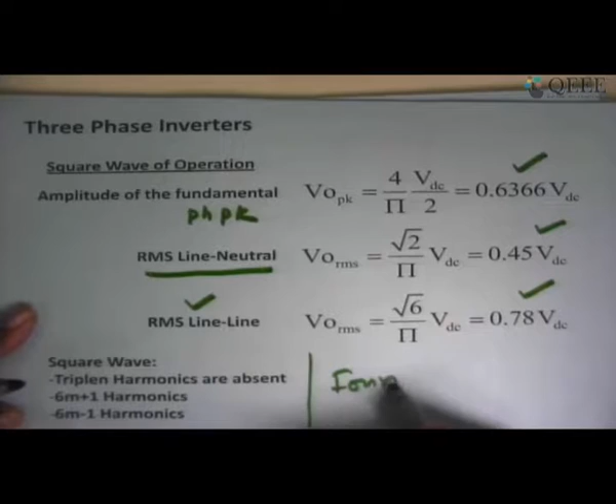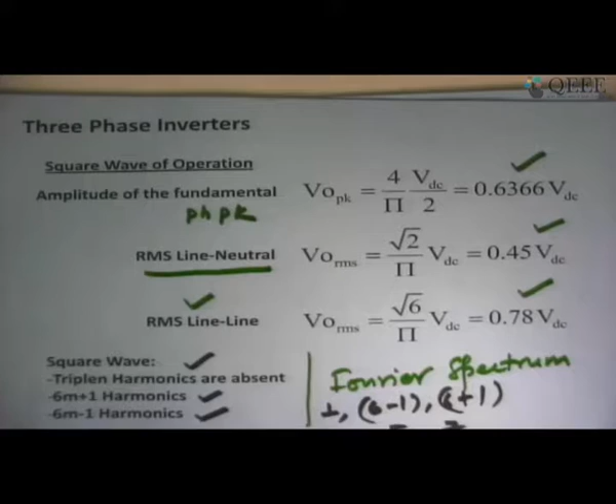So if you draw the Fourier or harmonic spectrum of this square wave waveforms, the triplen harmonics will be absent, because you have a symmetry, third harmonic symmetry is there. Secondly, you will get 6m plus minus 1 harmonics, where m is the fundamental. So for a 50 Hz output, you will get 300, 350, 250. So you will not get 300 because this triplen will not be present. So you will get fundamental, 6 minus 1, 6 plus 1. So this is 5, 7. Then you will get 12 minus 1, 12 plus 1.